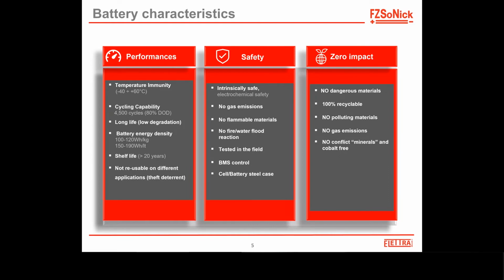We will never produce any gases in operation or even in worst-case failure modes. There are no flammable materials; the battery is basically made out of stainless steel, ceramic, and salt. There's no flood or fire water damage, and we have extensive testing, not only in labs but in the field as well. Our battery is made out of a very robust material, heavy stainless steel, so it's a physically robust design. In terms of environmental impact, we don't use any dangerous materials in it.